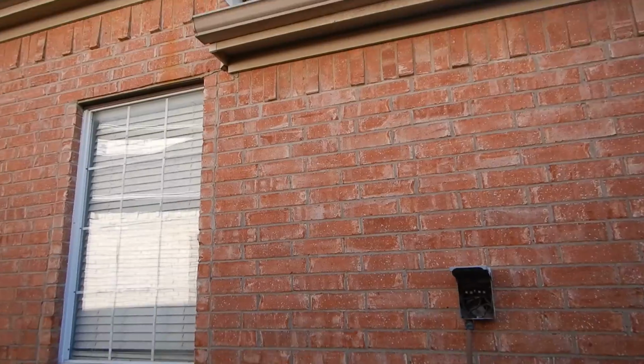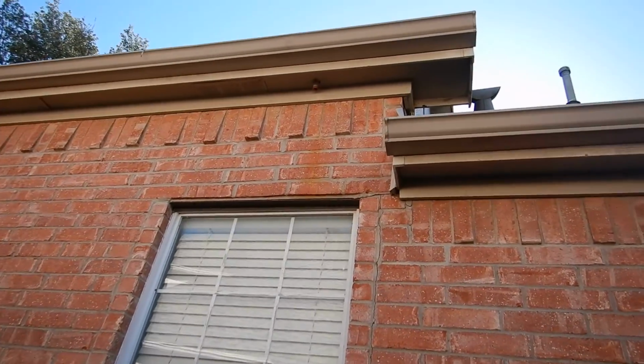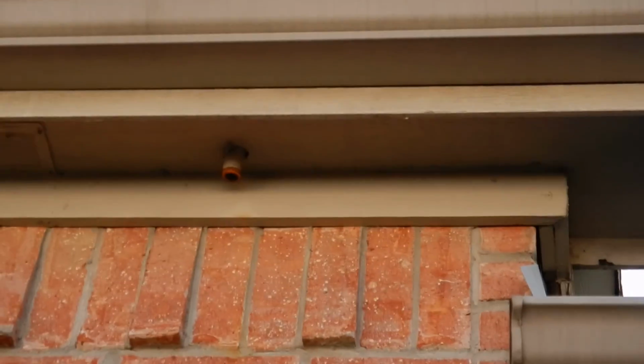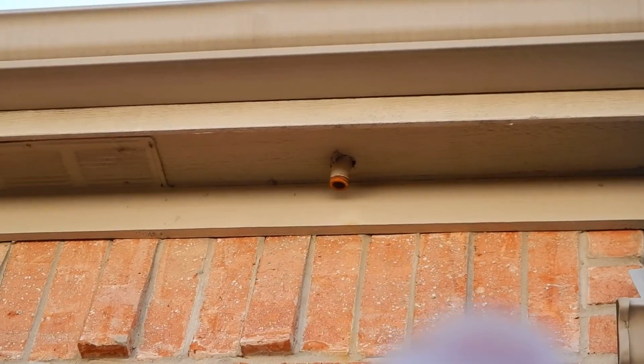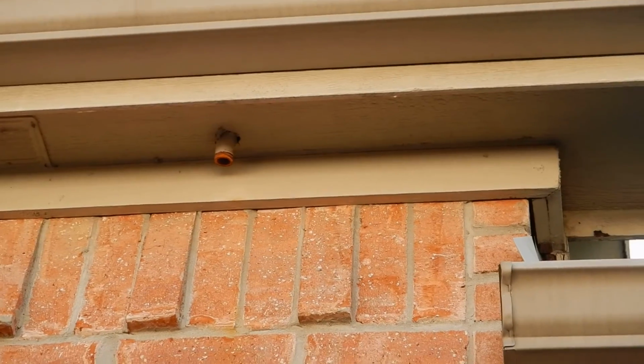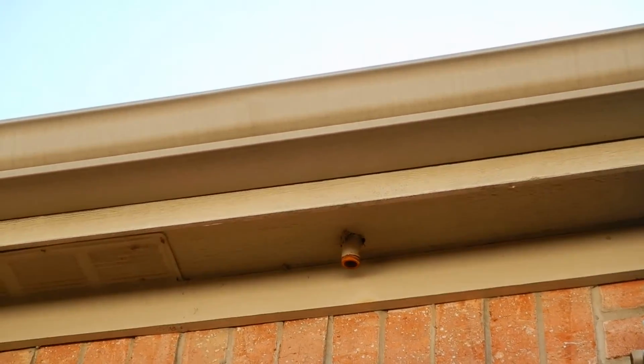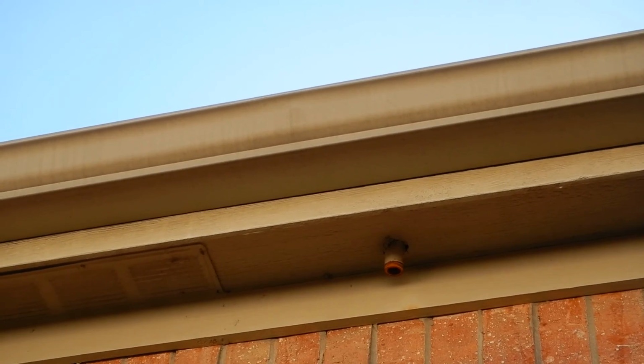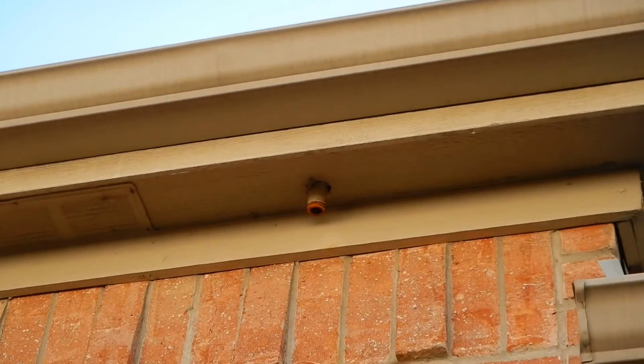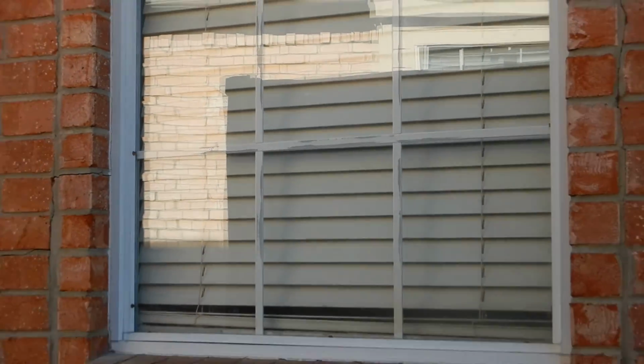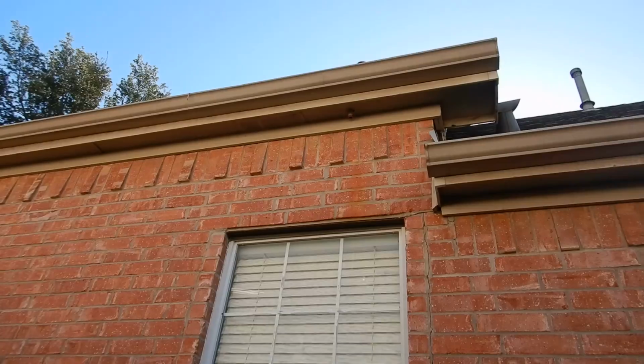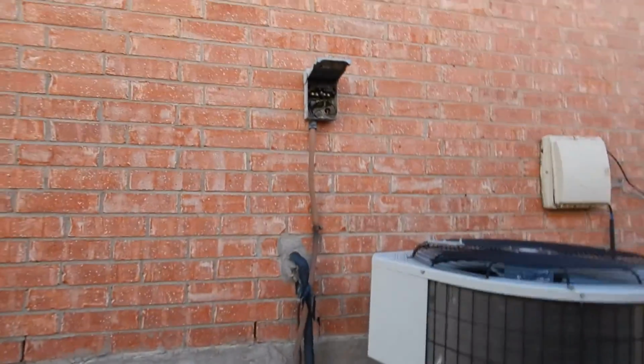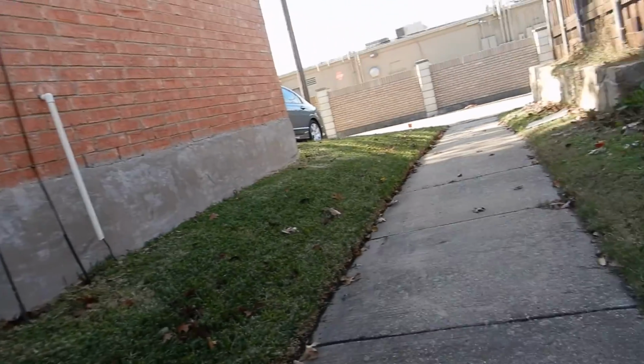Okay? Let's go to the clothes dryer. Oh, back to the air conditioner. I don't mean to yank you around, but see that pipe right there? Well, see the rust around it? That means rusty water's been coming out of that. And that pipe is the secondary drain line. It's the second drain line for the safety pan, so that if the primary gets clogged, the water comes out over a window. In theory, you can look out the window and see the water coming down. And when you do see the water coming down, you know that you have a problem.